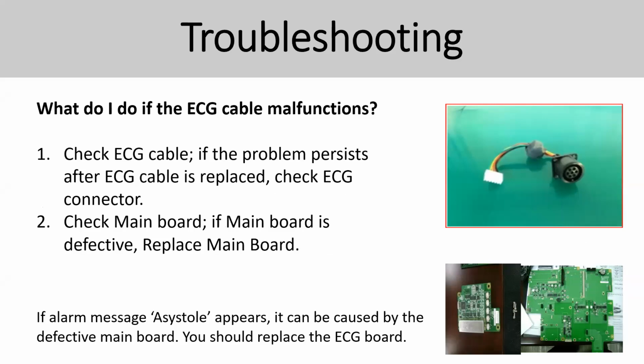ECG: normally you don't have any problem with the internal connector and the ECG board, you don't see much problem. The common problem that you're going to see on ECG is basically the accessory, the ECG cable itself. So just cross-check the cable by using the ECG simulator. If it doesn't work, get another ECG accessory, exchange it, and try with the simulator again. If it works, that means the accessory is the problem, not the internal part.